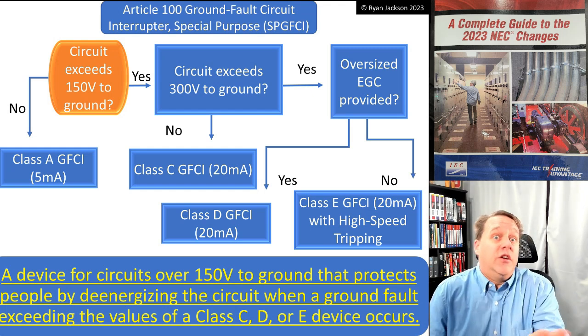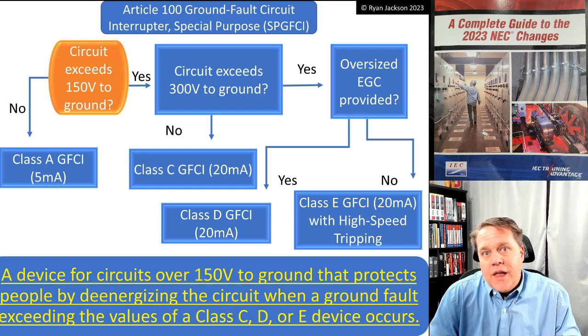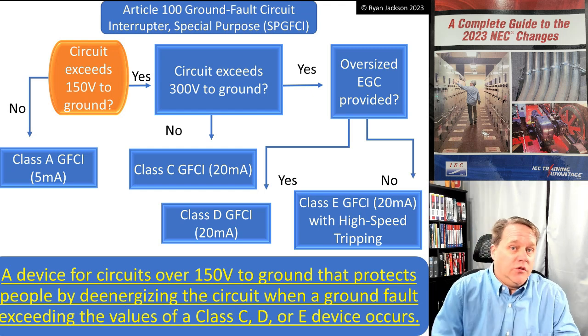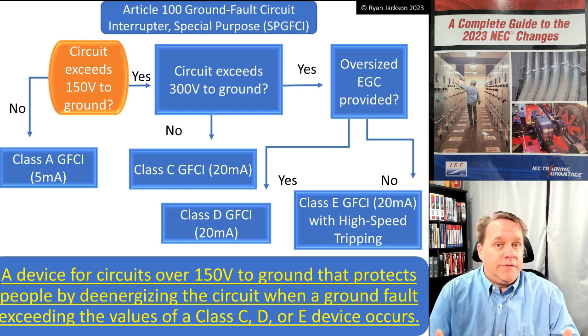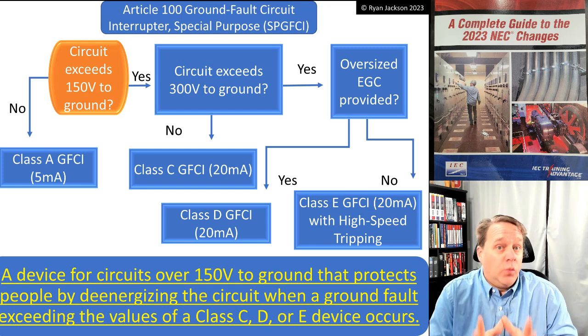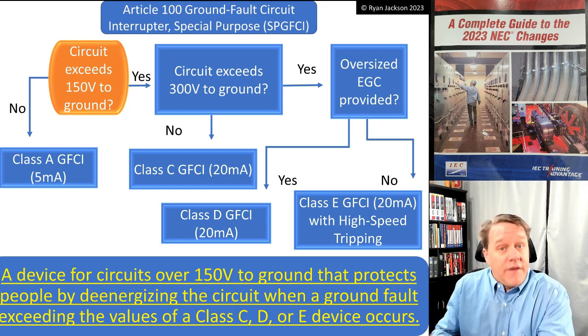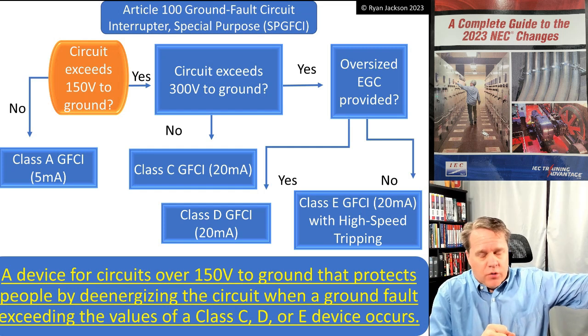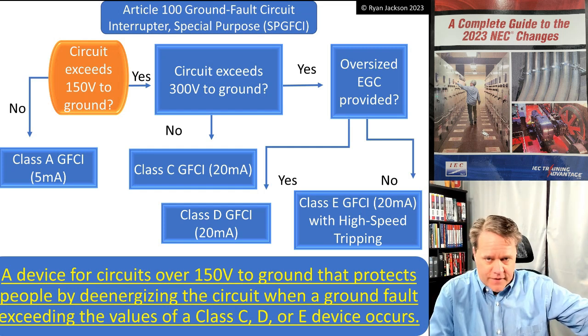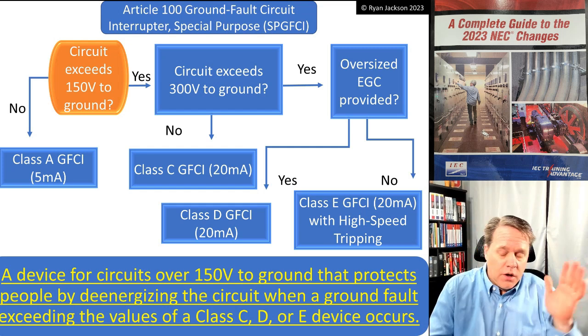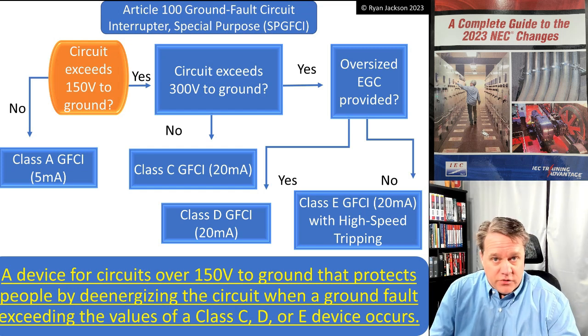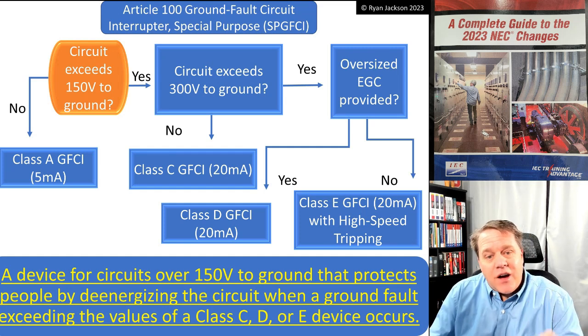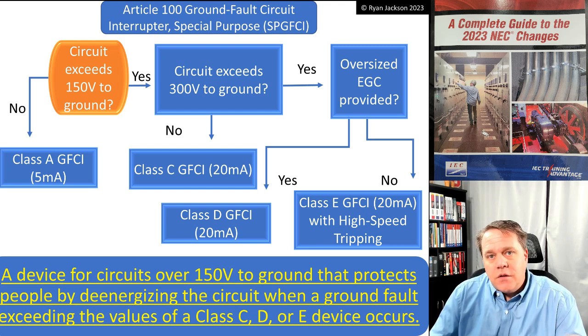Class A GFCI devices have been around since their invention back in 1968. There was also a Class B GFCI device, but that was only for underwater swimming pool luminaires and was only around for about three years — just long enough to prove the concept that GFCIs could prevent fatal electric shocks. Class B has not been around for over 50 years. Class A is all we've been using for 50 years — until now, with the introduction of Class C, D, and E ground fault circuit interrupters.